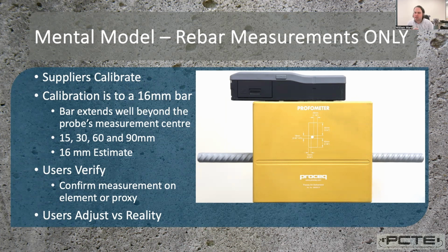Now, calibration is a process where we do two things. We compare performance to a standard. That's our check blocks here. And we may also adjust the internal settings of the cover meter so it can measure the test block accurately. Now, a supplier does the calibration process and does it the same way every time, to a manufacturer procedure.